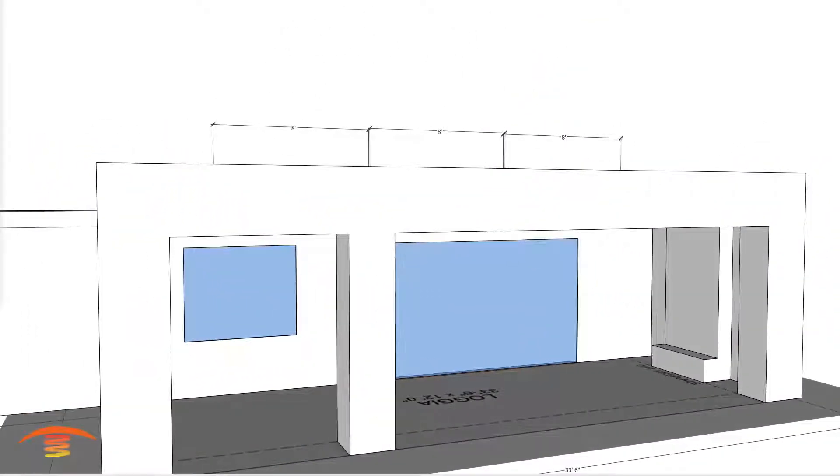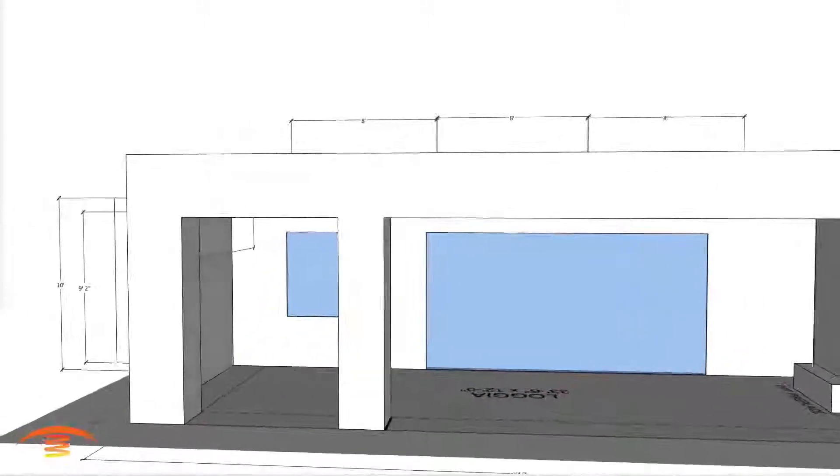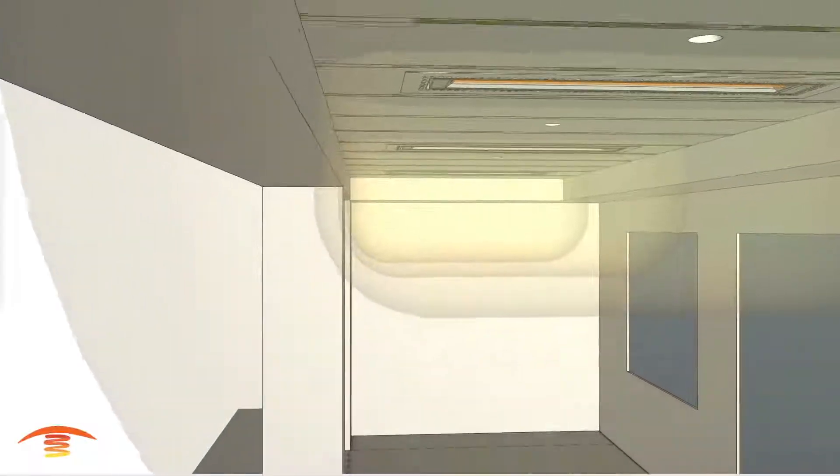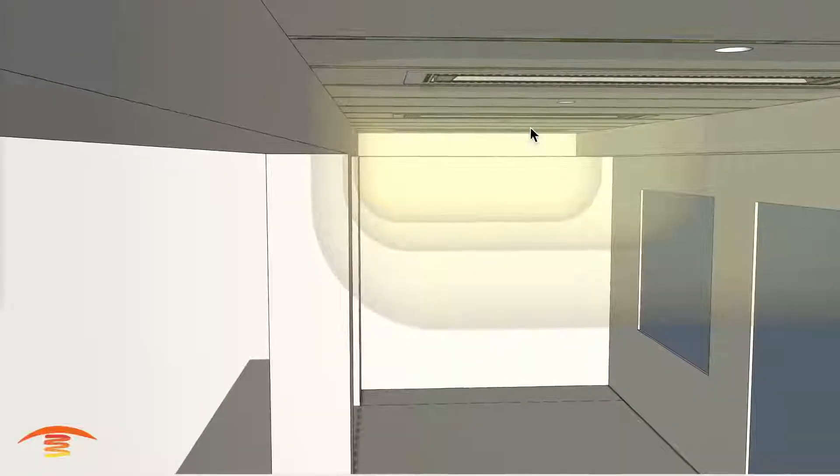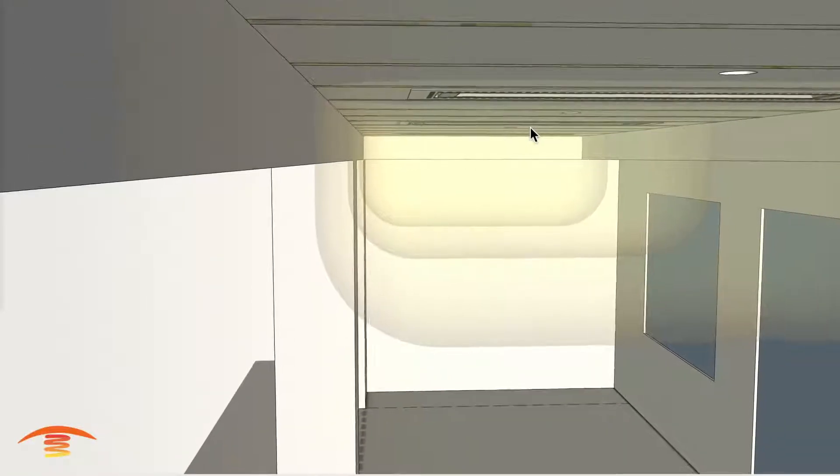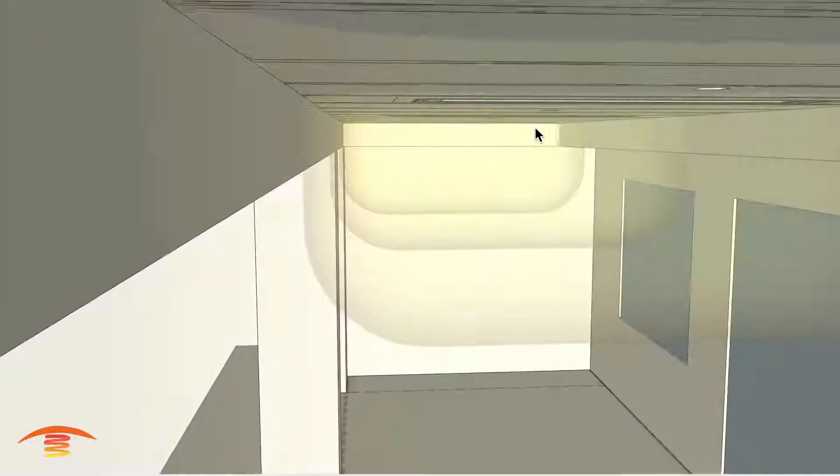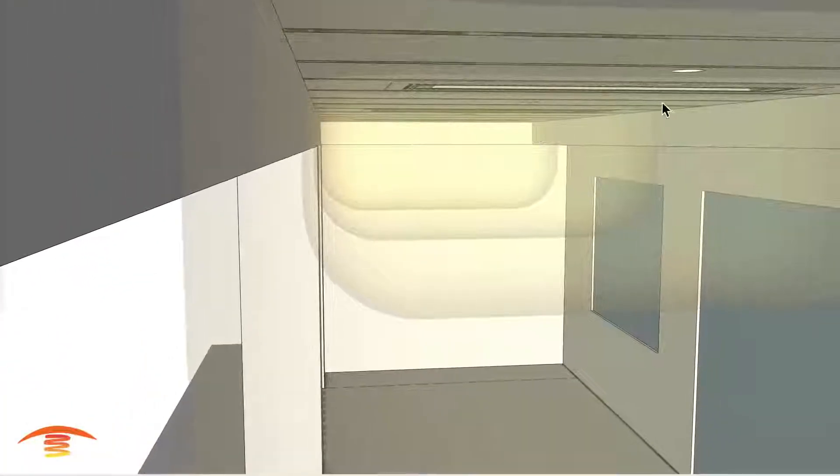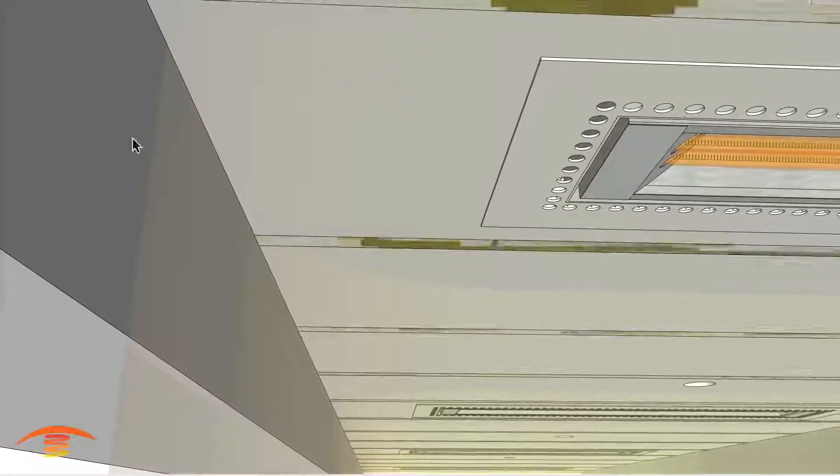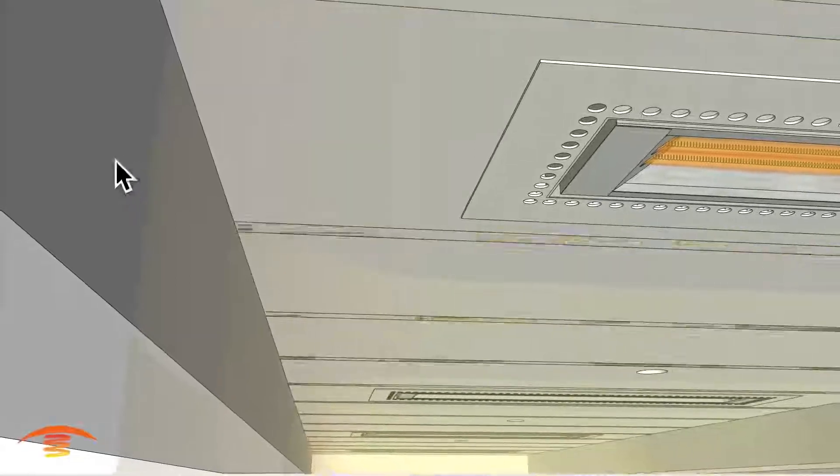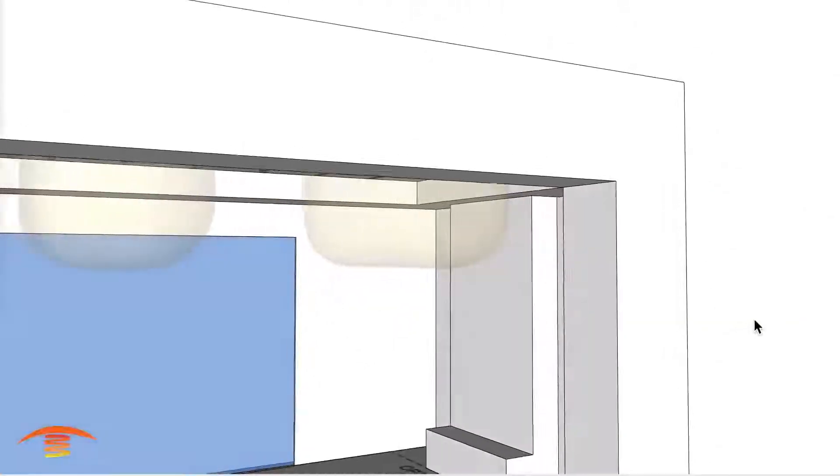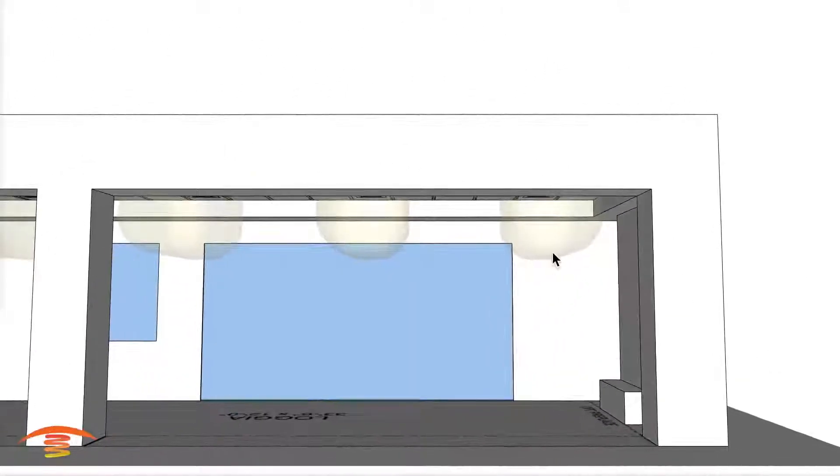Let's look at clearances. So you need 18 inches of clearance below each heater inside the flush mount kit and one hour fire rated drywall. We'll maintain the clearance above, but out here you need to have 18 inches from this edge of the heater to any combustible item to the left. And then of course there'll be 36 inches down below the heater. And that's true on all heaters.